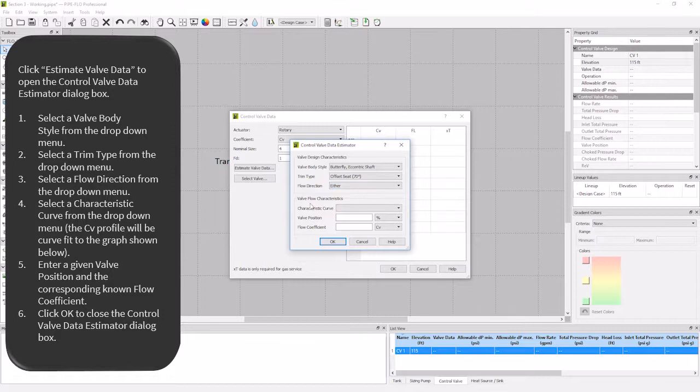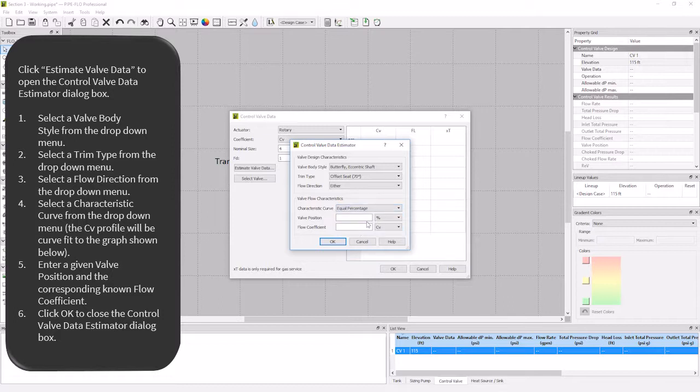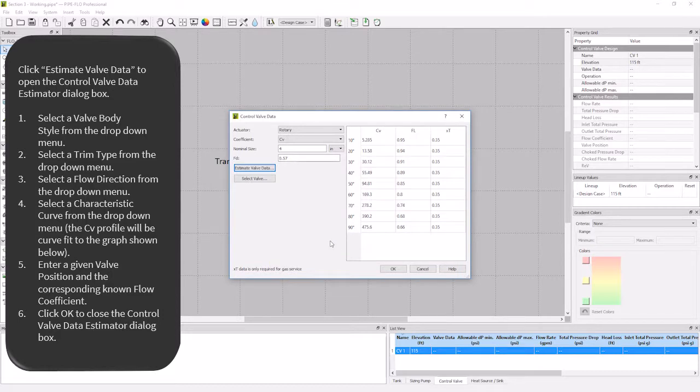And now that my valve type is selected, it is time to estimate the curve. My characteristic curve is equal percentage, with a C sub V of 400 at 90 degrees open. I will click OK, and now all the information required for my valve is filled in.